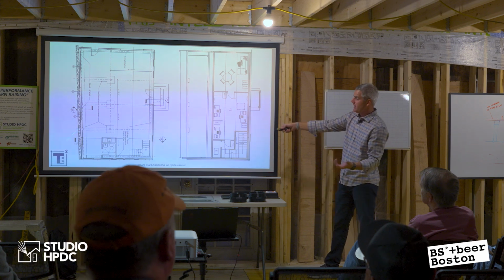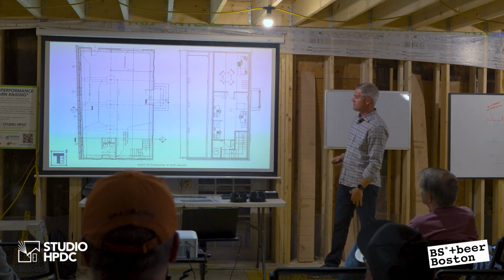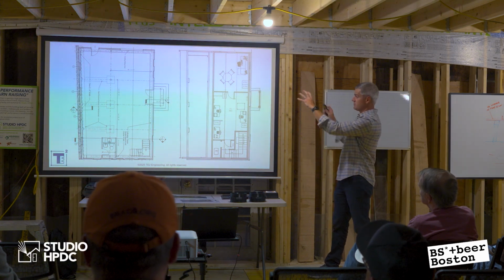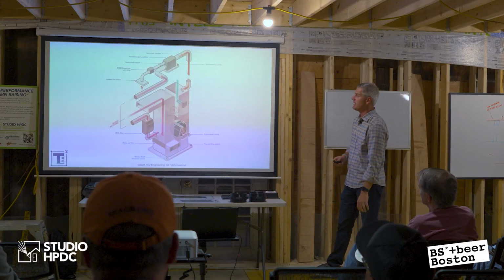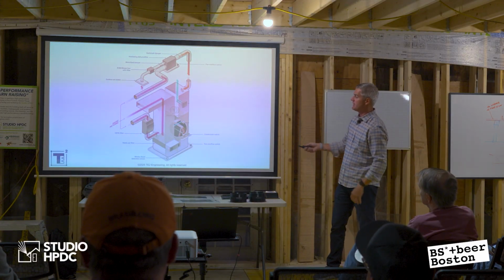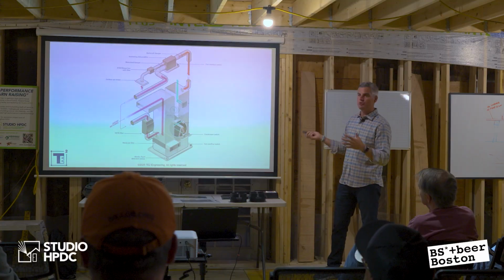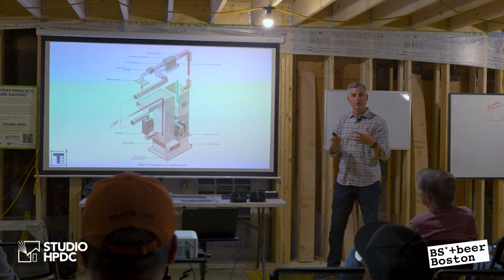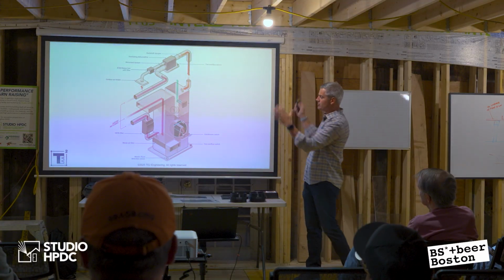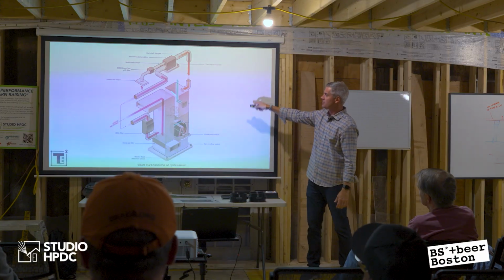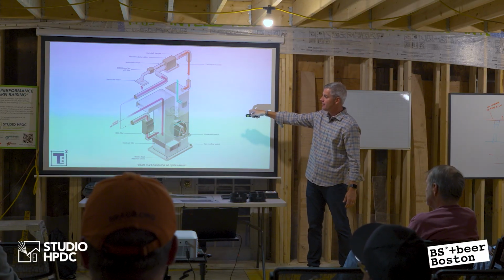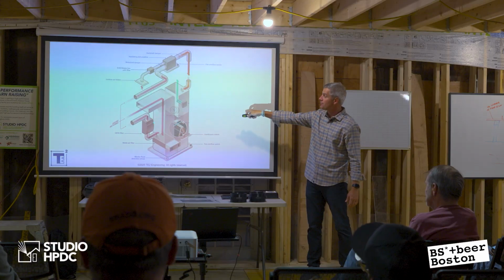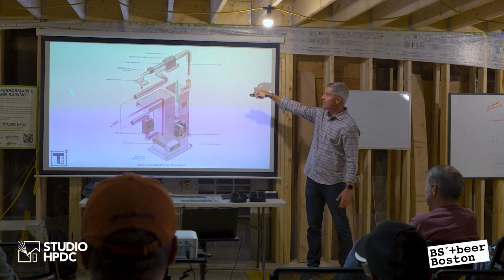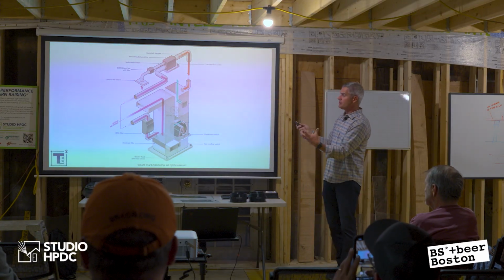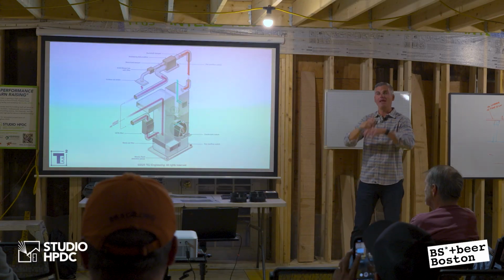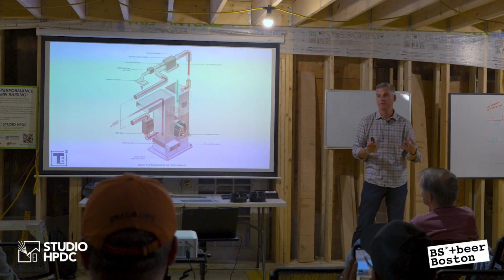Obviously here's the first floor plan, here's the second floor plan, kind of I was laying out, and I've got some thoughts in terms of how the systems would actually be laid out. We'll come back to that in a second. And then a lot of people ask me, well, how would you duct these systems all together? This is just a conceptual snapshot that I can have an air handler with a supply trunk and a return trunk, and I can add, let's say, a media filter, I can add a HEPA filter, I can add a ventilating dehumidifier, I can add an ERV, I can add that all to this system to make it what I call the ideal or optimal HVAC system for the space.